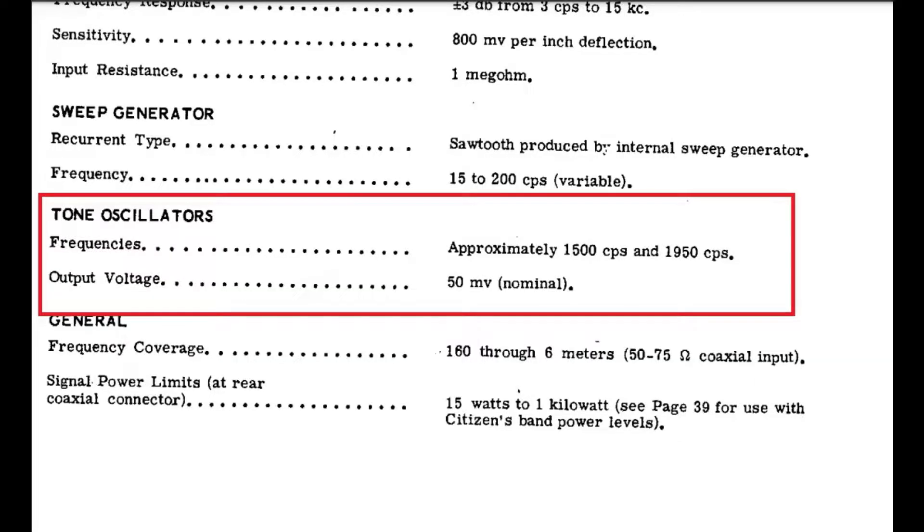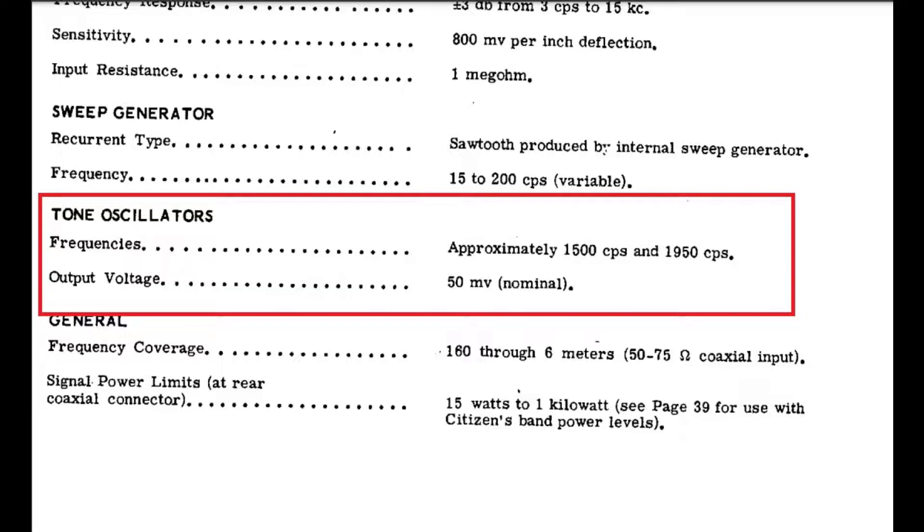Okay. So what you can see here in the specs is that the frequencies should be approximately 1500 Hertz and 1950 Hertz. And so we're not that far off. We're pretty close at 1600 Hertz and 2000 Hertz. So overall, I'd say this is great, fine, and good enough for government work.